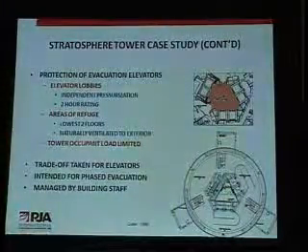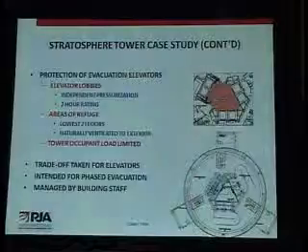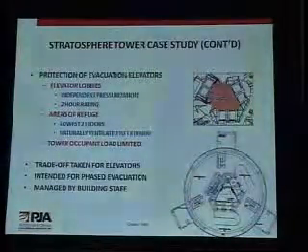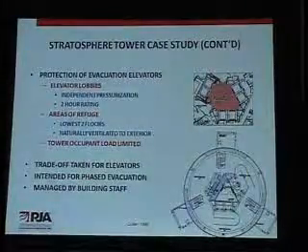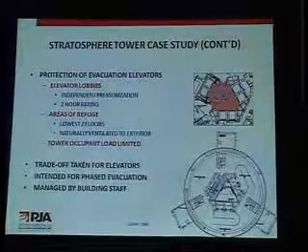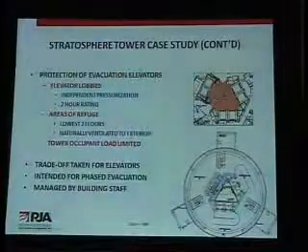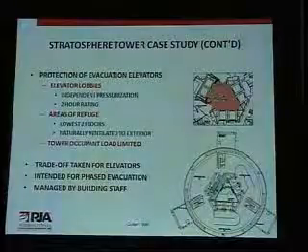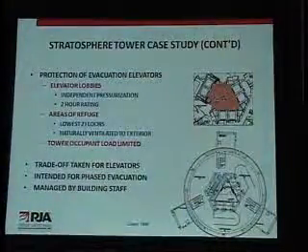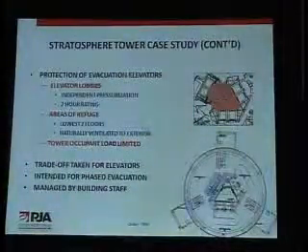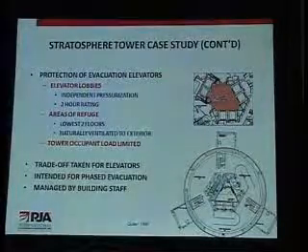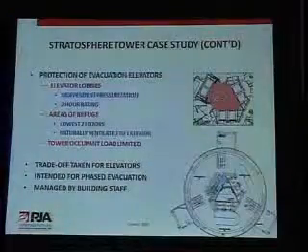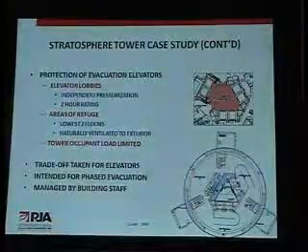It's the 2 lowest floors of the upper portion of the tower, and it's separated from the tower by 3-hour floor construction. It's open to the exterior, so it's naturally ventilated. Because this is an assembly occupancy space, people have to purchase tickets to enter. The tower occupant load is limited so that the occupancy within the tower can only be equal to or less than the number of occupants that could be evacuated in 1 hour using the elevators.